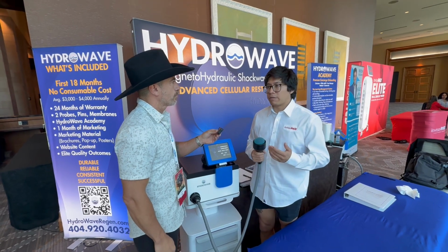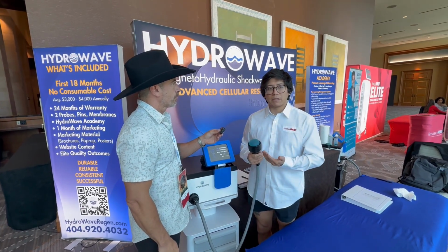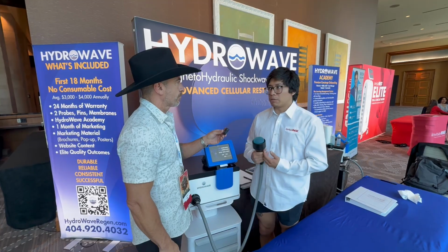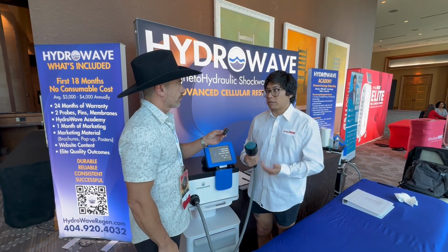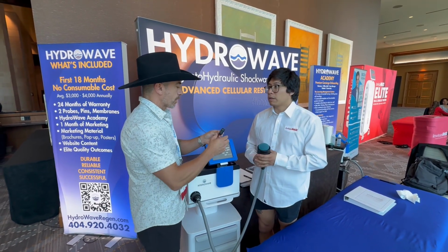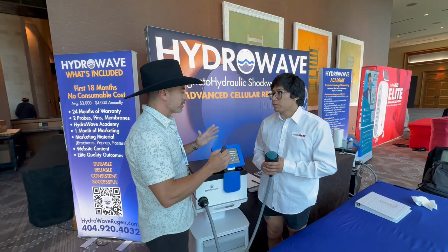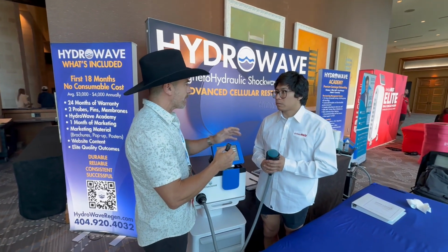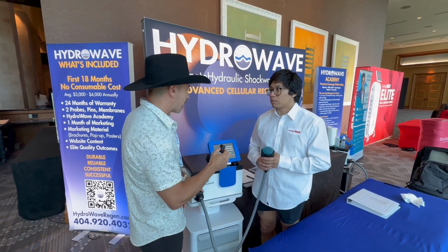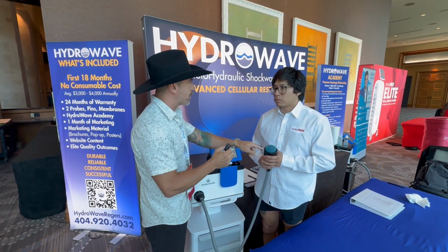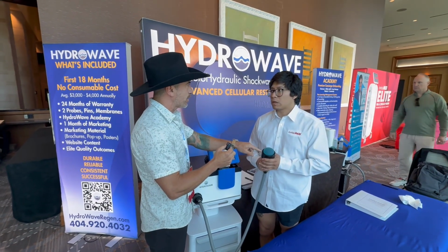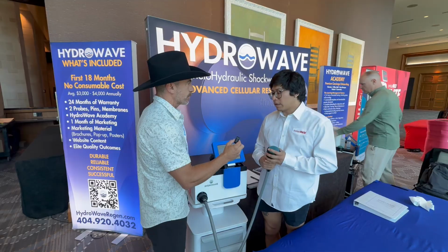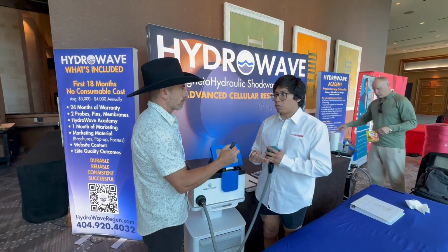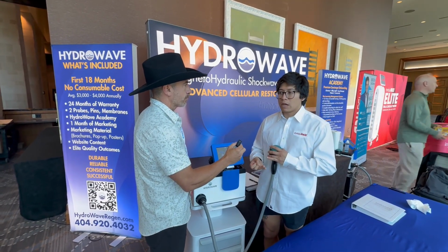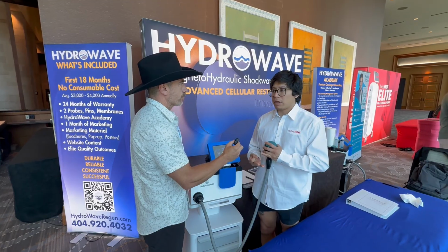What we suggest is every time you change the water, just inspect the pins. If you notice any corrosion, usually like black spots, just go ahead and replace those pins with the other pins that we've included. Okay, so if I'm understanding this correctly, the same corrosion is happening. It's just happening here at the pins versus happening inside of the actual applicator with the other devices. Yes, and it makes it a lot easier, so then that way you're not sending a whole probe in to us for us to do maintenance. You can continue doing treatments and you don't have any downtime.